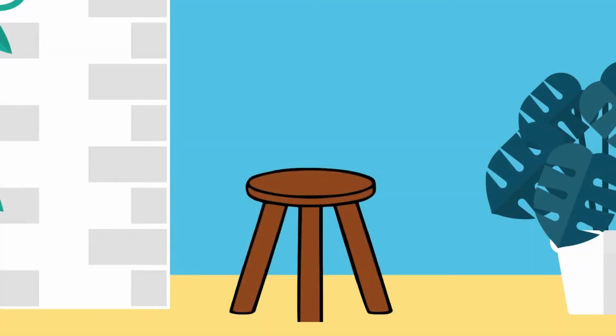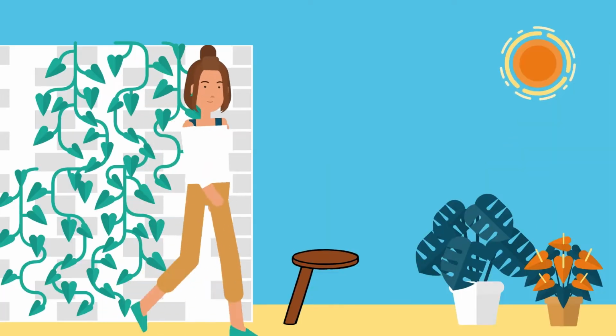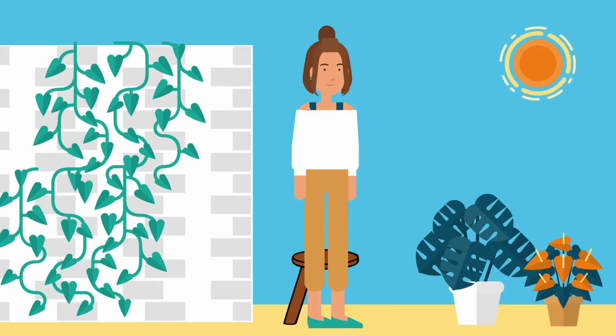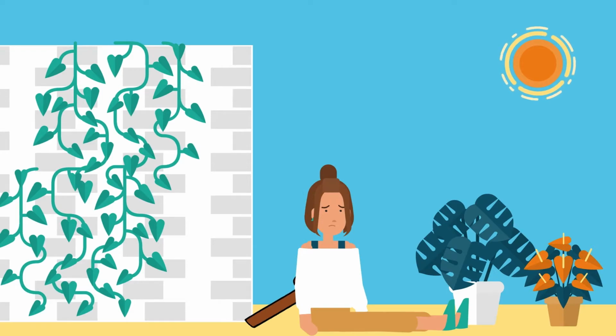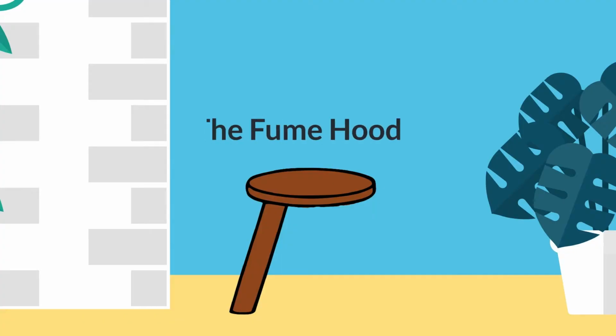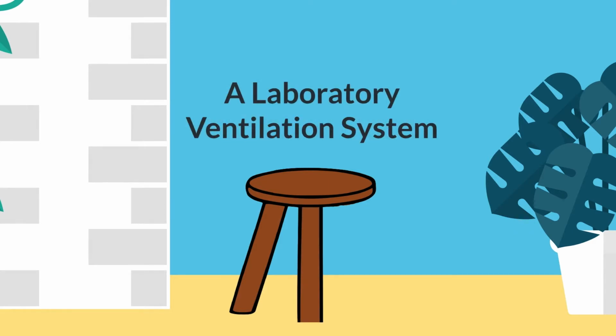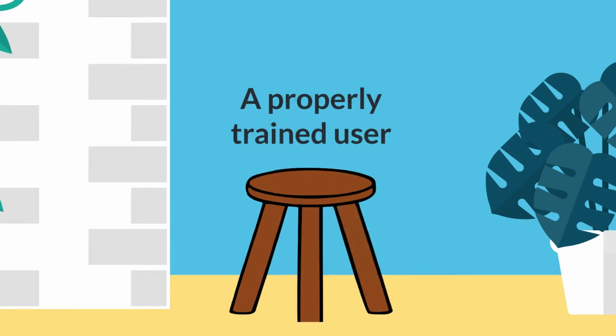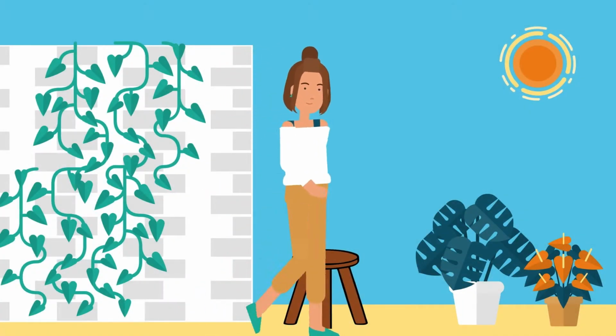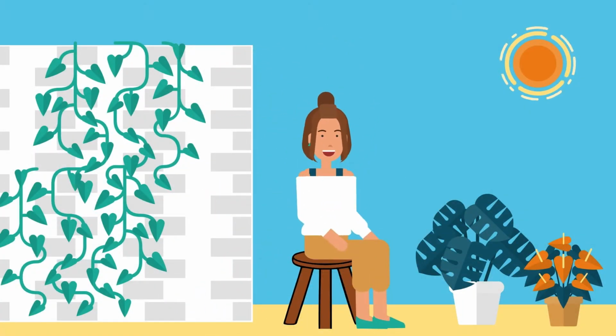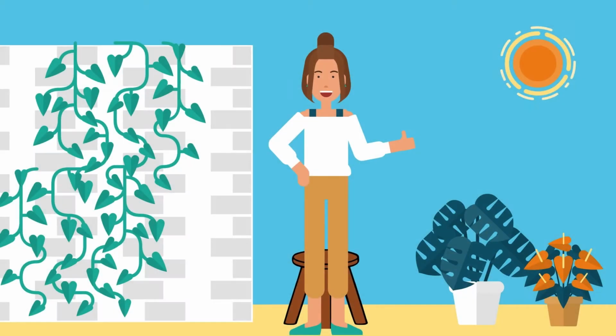The fume hood is much like a 3-legged stool. To be stable and function properly, the stool needs 3 even legs. The same is true with the fume hood. Its legs are the fume hood itself, the laboratory ventilation system, and a properly trained user. So unless the fume hood's performance is viewed in this holistic way, the fume hood will not function properly. All 3 legs must be balanced and functioning correctly to protect the user.